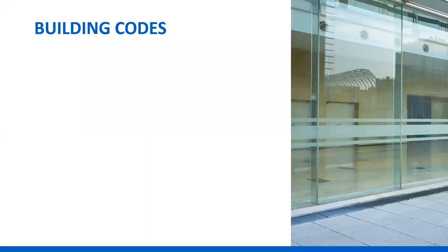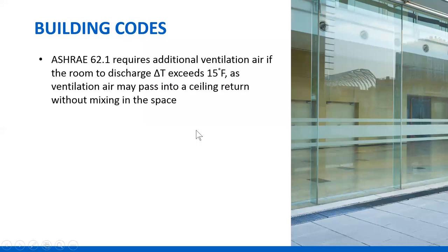We do have to deal with the rules. ASHRAE 62.1 says if you put warm air out of the ceiling, some of the ventilation air is going to pass out through the ceiling return, short circuiting. If the delta T — discharge to room differential — exceeds 15 degrees, it's strongly recommended that you increase the ventilation rate by dividing the required minimum ventilation by 0.8, which results in a little over 20% increase in ventilation.